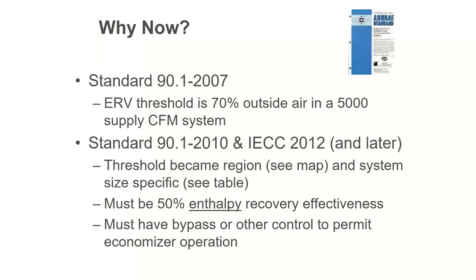When are they code required? Well, it used to be not very often. Stuff that had 70% outside air on 5,000 CFM systems. So not a lot of stuff. But since 2010 ASHRAE, which is the 2012 energy code, there are new rules. One of those rules is you have to be 50% enthalpy recovery, meaning you can't do just sensible. You have to do sensible plus latent if you want to get 50% of the total.